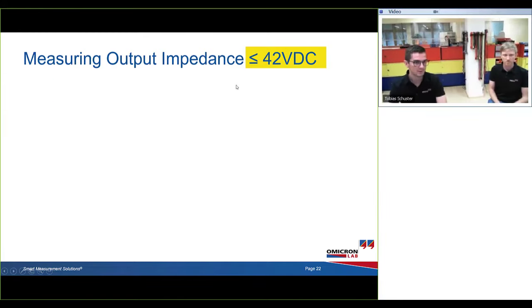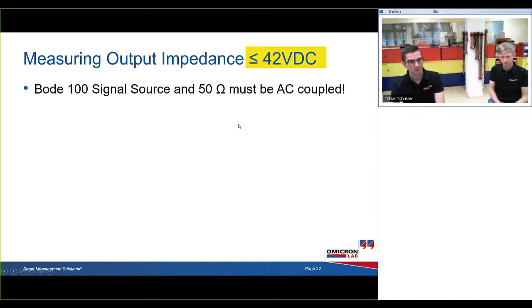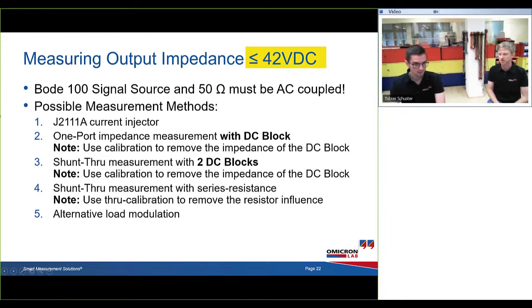If you have voltages up to 42 volts DC, then you have to take care of the Bode 100, especially the output, since there is a 50 ohm resistor which is AC coupled. Also, the input, if it's set to 50 ohms, you cannot connect 42 volts, but if it's set to high impedance, it can withstand up to 50 volts. So then that's not a problem. To do so, you can use the current injector. That's the easiest method if you want to measure up to 42 volts. Then you can also use the one-port with a DC block. If you do so, you need to do a calibration to remove the influence of the DC block.